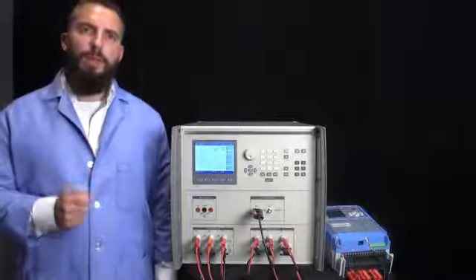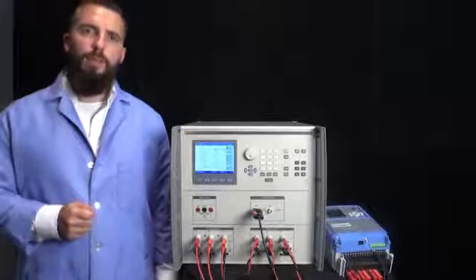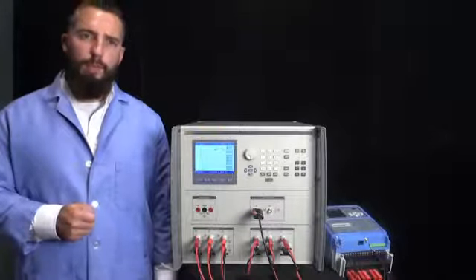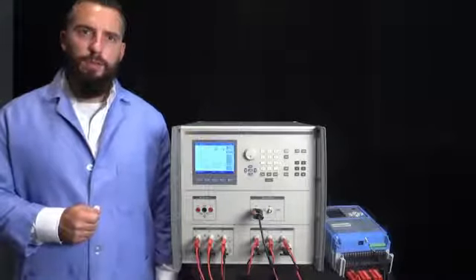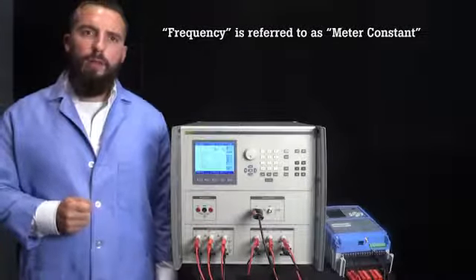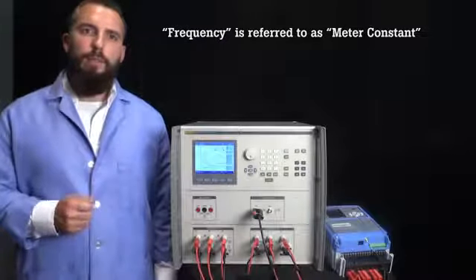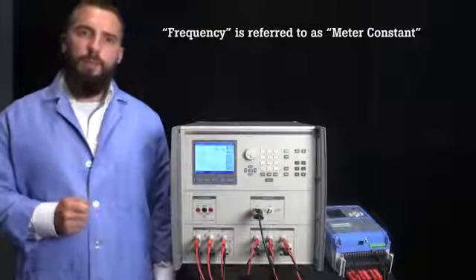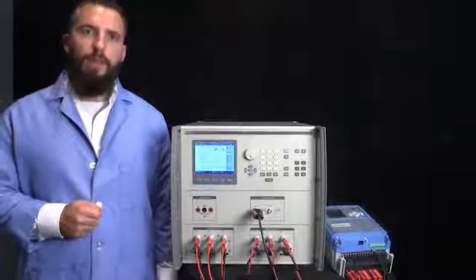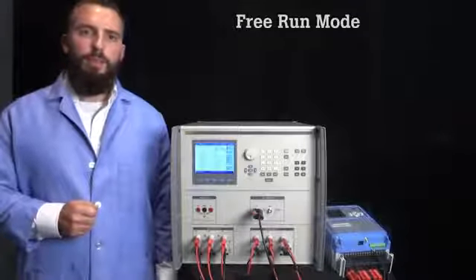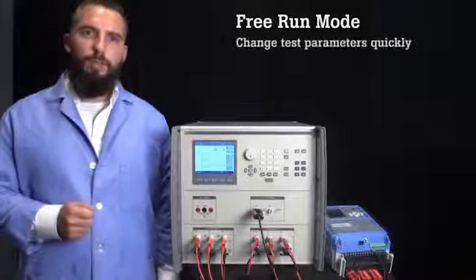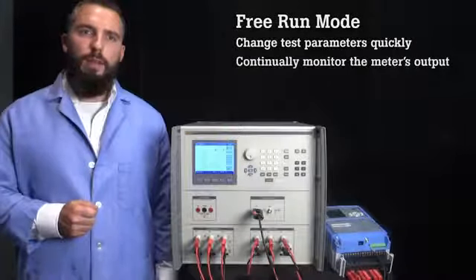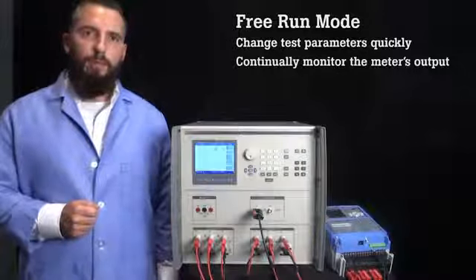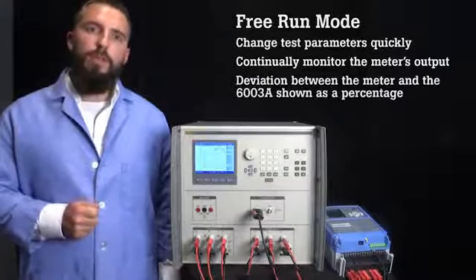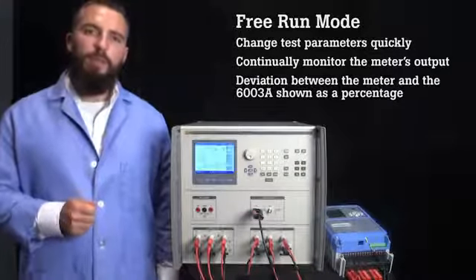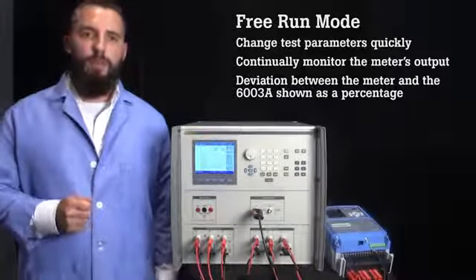One of the biggest pain points in energy meter calibration is determining what the correct frequency of the meter output is, based on the energy it is measuring. For reference, the frequency is also commonly referred to as the meter constant, and matching the meter constant to the calibration system can be confusing. The 6003A has a mode called free run that simplifies this process and allows you to quickly change the test parameters while continually monitoring the meter's output to verify that the correct meter constant is being used. The deviation between the meter and the 6003A is continuously calculated and shown as a percentage on the display.